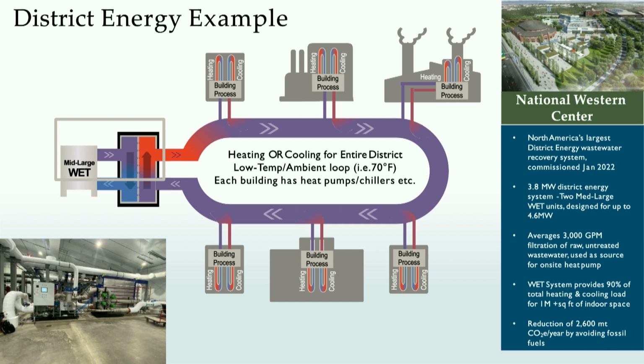Some buildings are dominantly cooling, like the supermarket. Others have diversity within their own building, both heating and cooling. But the net effect is that as buildings draw energy off the ambient temperature loop and others put energy back in, it balances out. We're providing a 55-degree minimum ATL temp and 78-degree max ambient loop temp to all these buildings throughout the whole campus.